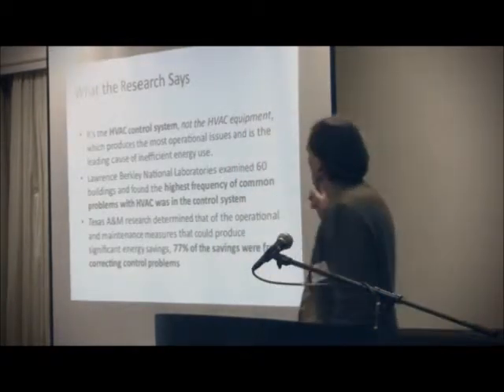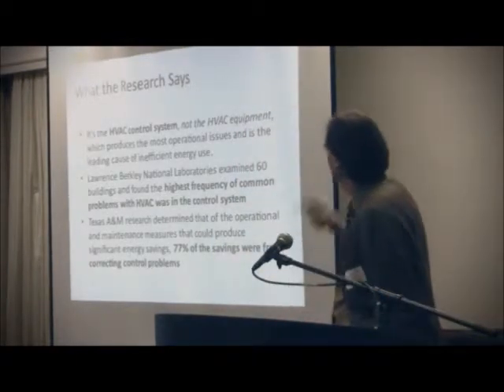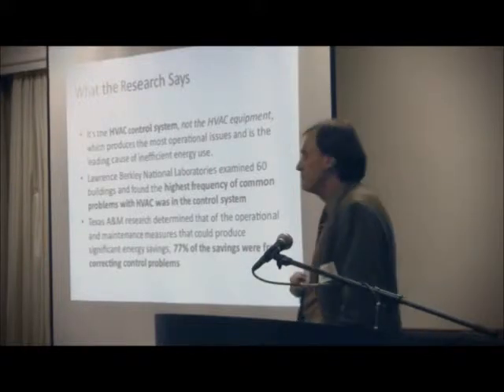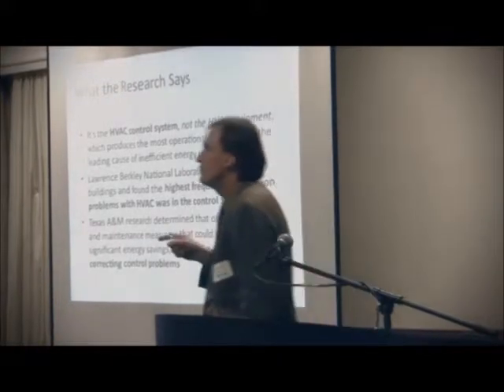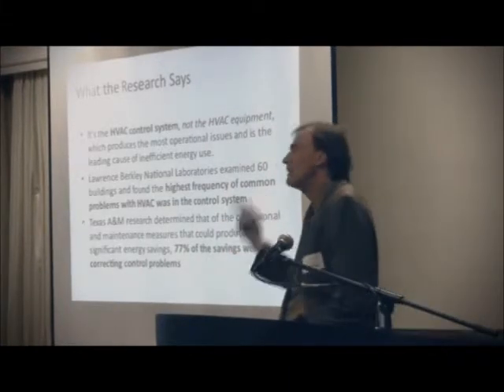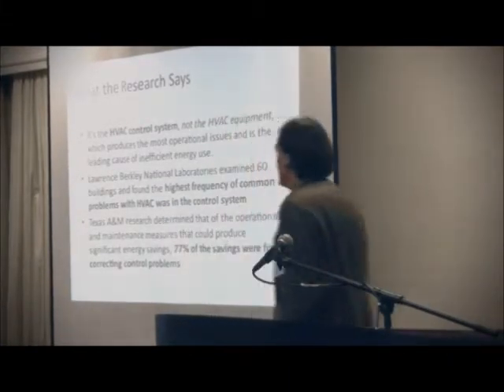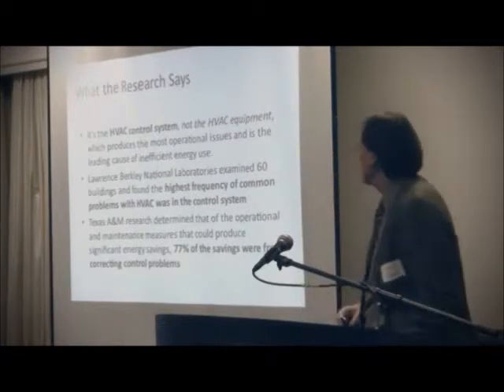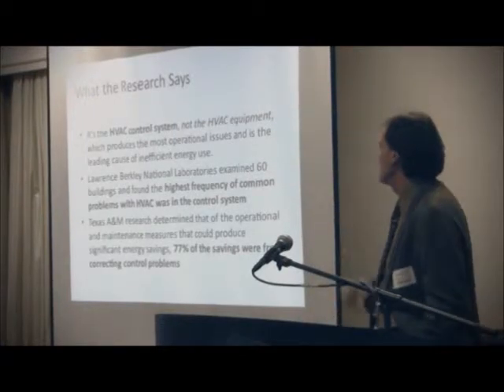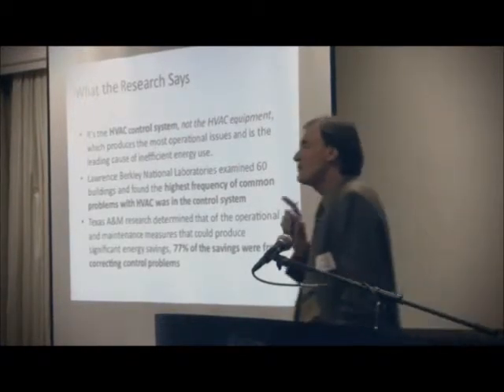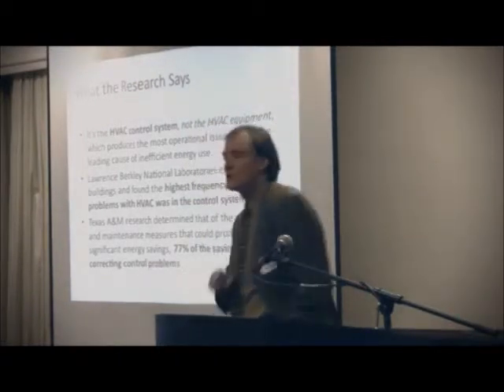Lawrence Berkeley National Labs did a study of 60 buildings, and the highest frequency of problems was with the control system—overwritten, not programmed right, algorithms not right, not running as expected, assumptions were wrong. 77% of the savings Texas A&M found in a research project came just from correcting control programs, not swapping out chillers or air handlers.